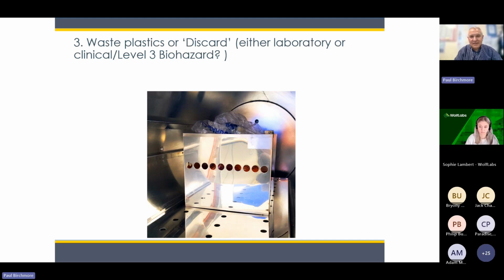So then moving on to another very standard type of load that's going to go inside the chamber, waste plastics or discard. In most cases, it's let's call it biohazard 1 and 2, but it's potentially up to number 3 biohazard level, BSL 3. We stop there. In some very specific labs in the UK, there may be a requirement for BSL 4, but in our laboratory product range, we go up to 3.